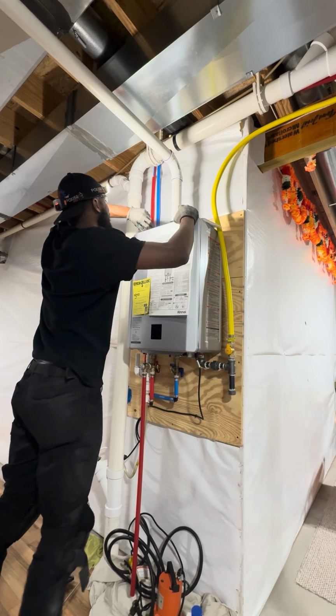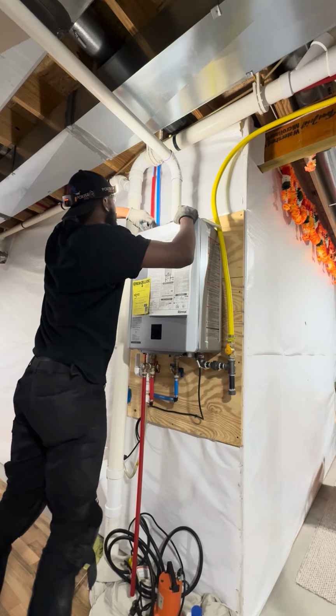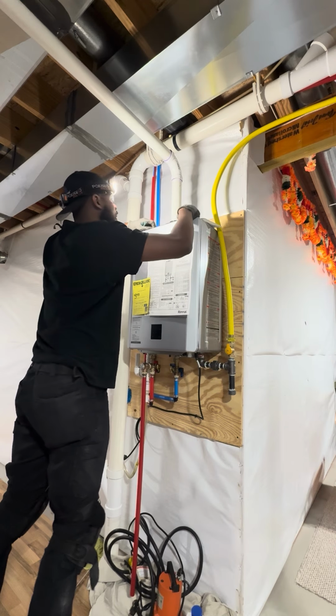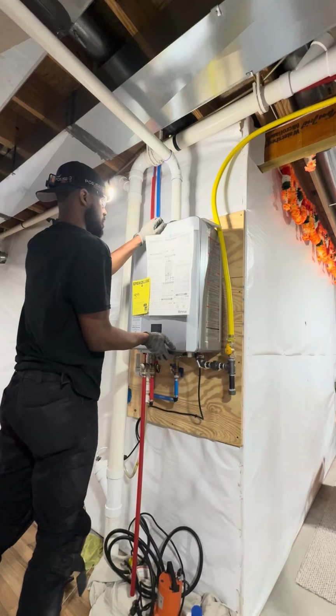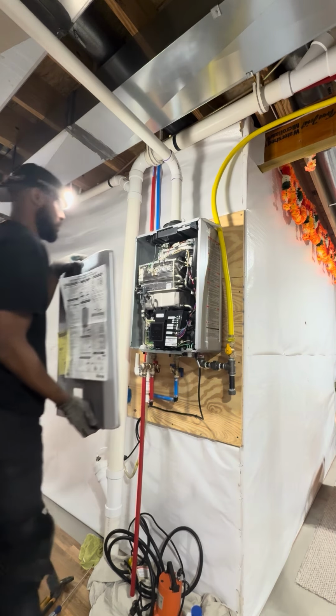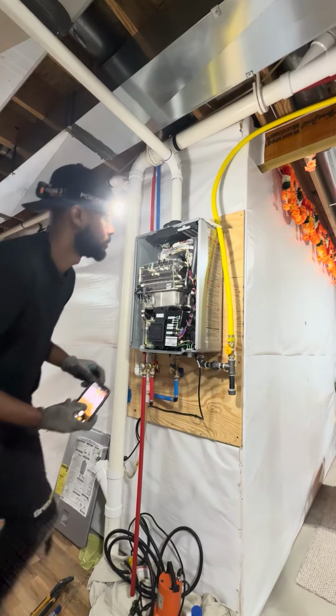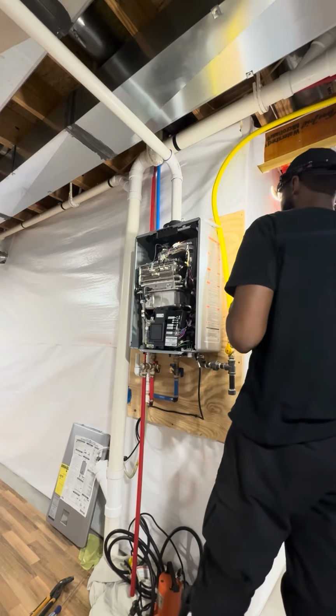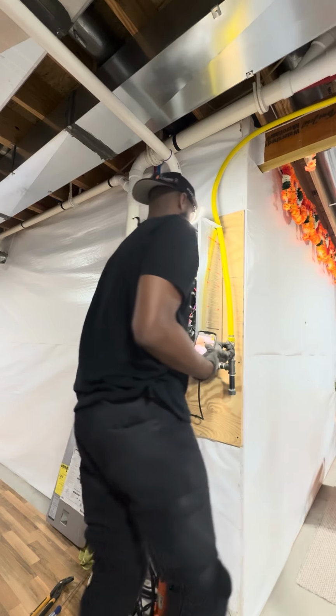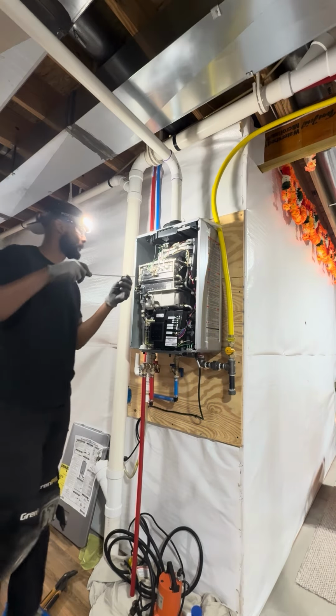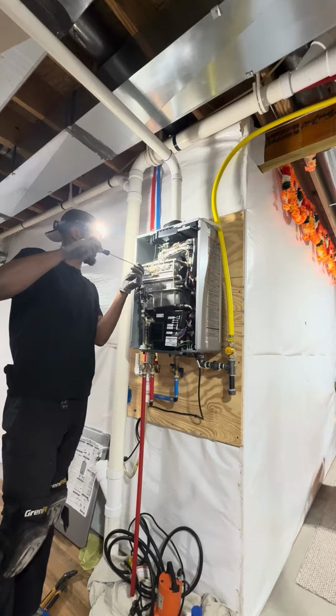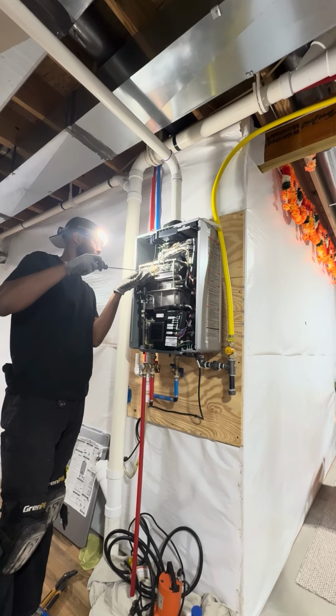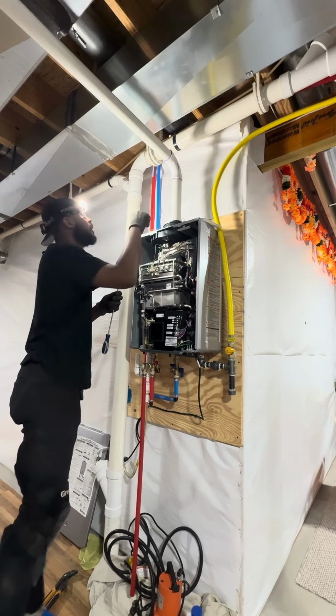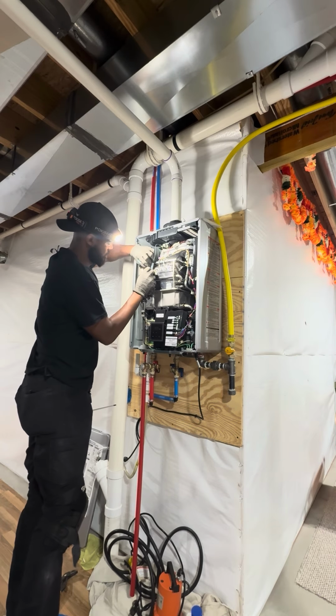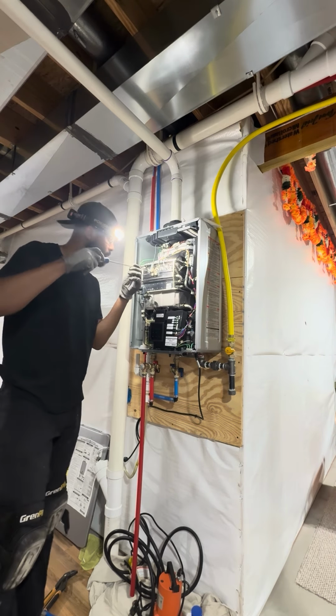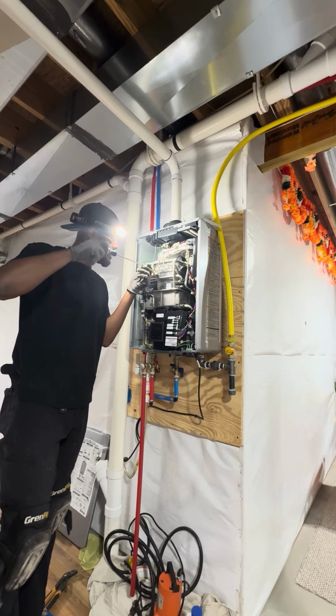I'm taking the doors off to see their wiring and everything else inside, like the heat exchanger, making sure everything is connected. I'll turn off their gas as well so it won't be seeping into the system since it's not going to fire. So with this, I'm checking their flame sensor and igniter as well.